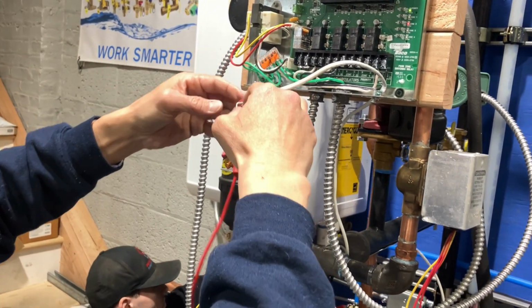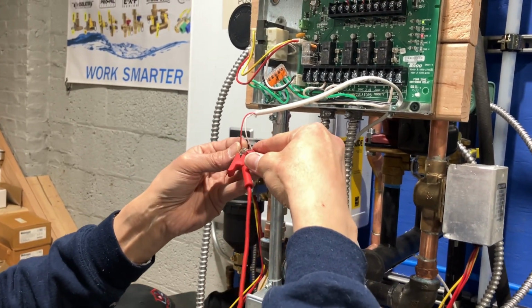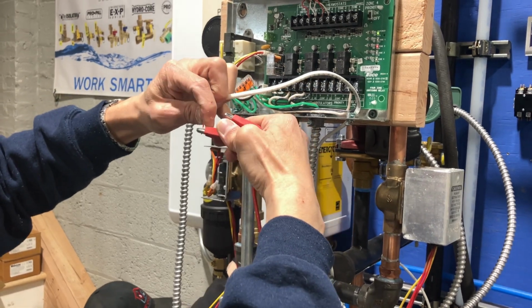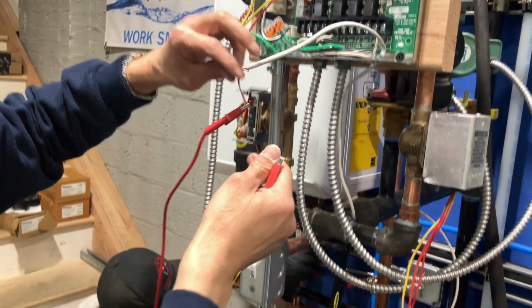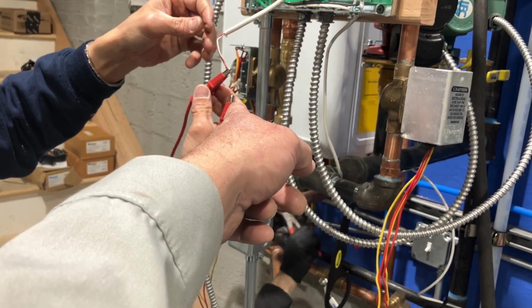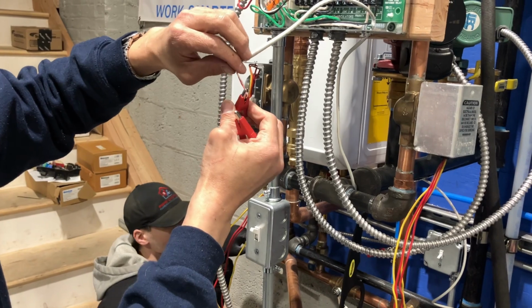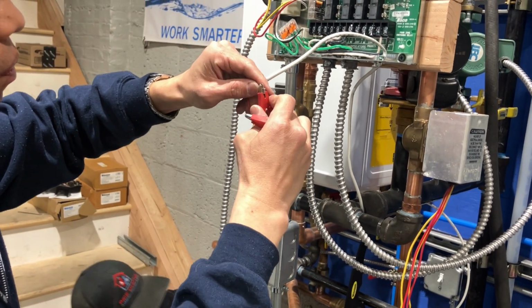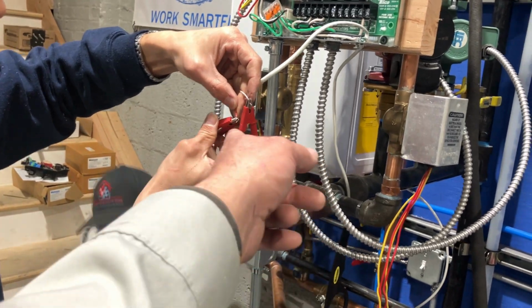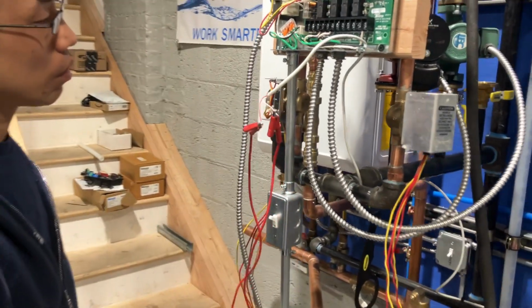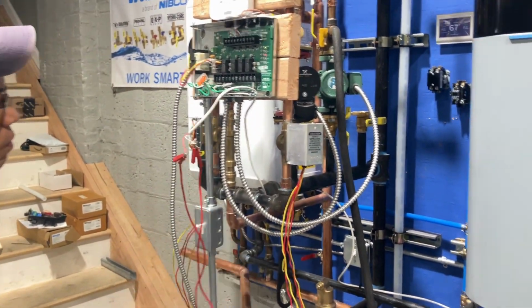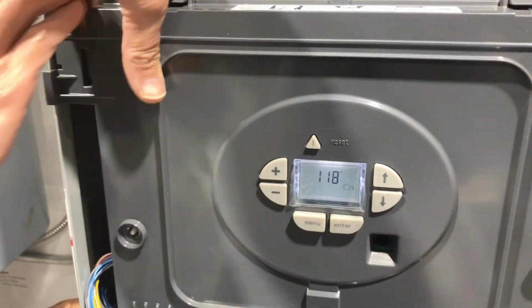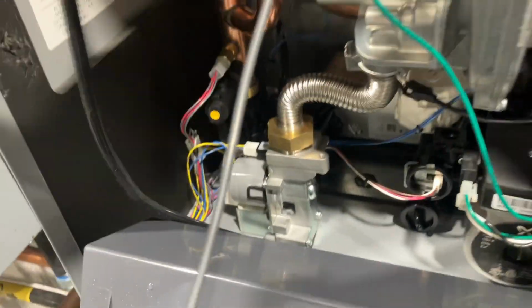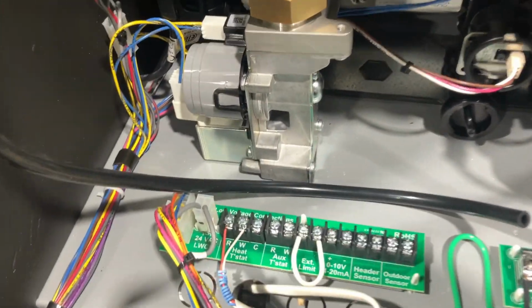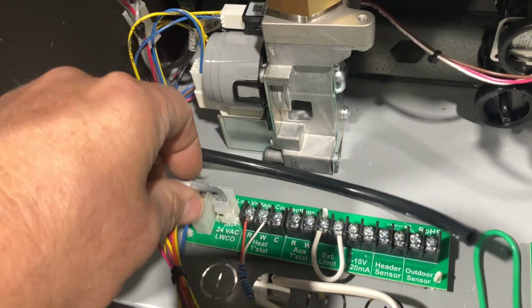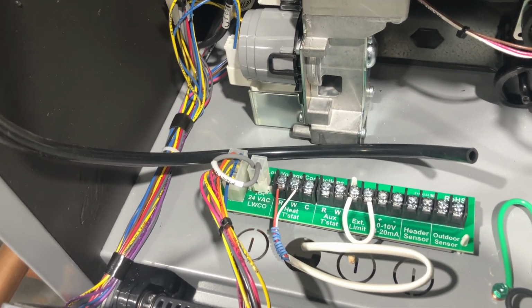Okay, so now, it's fine. Our connection to the boiler, I wouldn't do it that way. I would do it the way you had it, because you're gonna have one end dangling and there's 24 volts there. Right? Because if you have both connected, if this hits something like metal, you could fry the transformer. So now you have it jumped out going to our boiler, right? Which is R and W there, right? Just confirm.